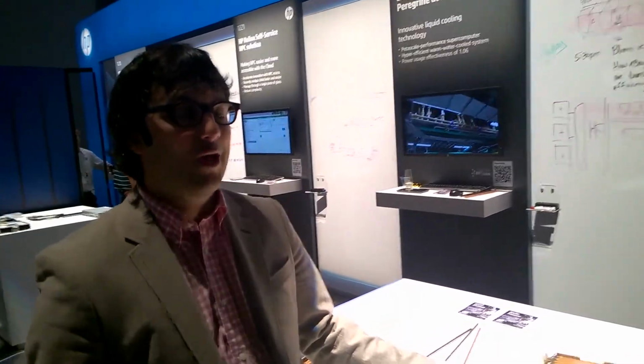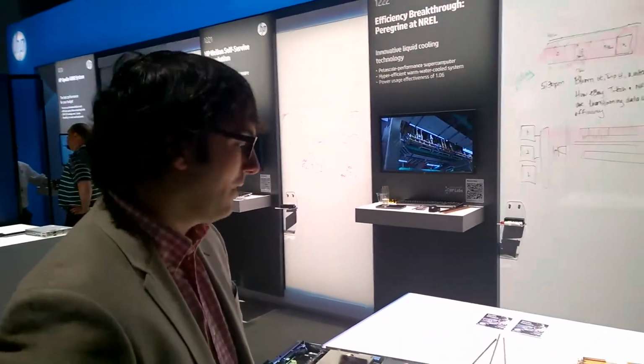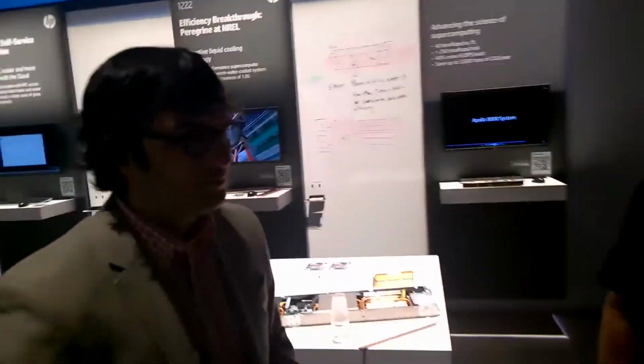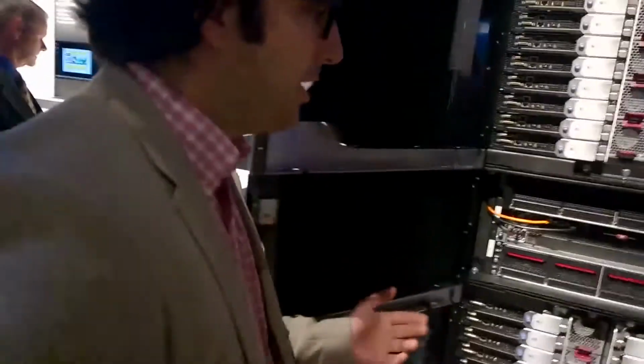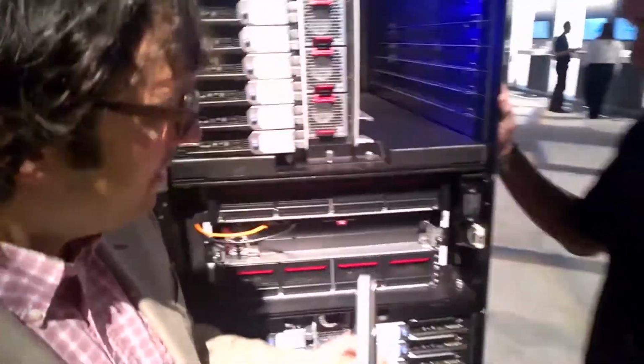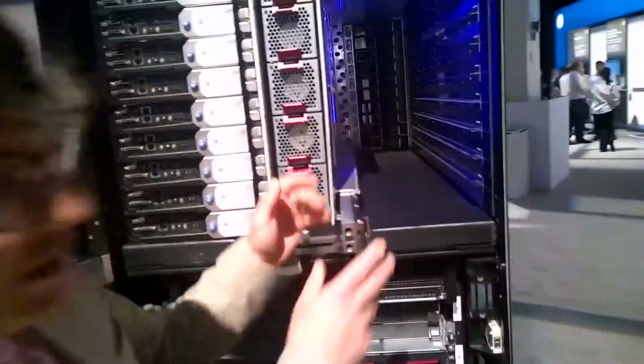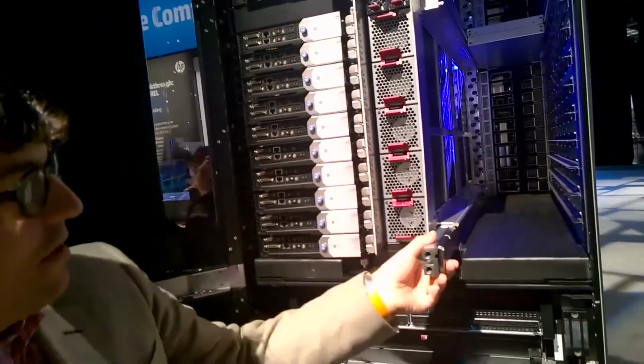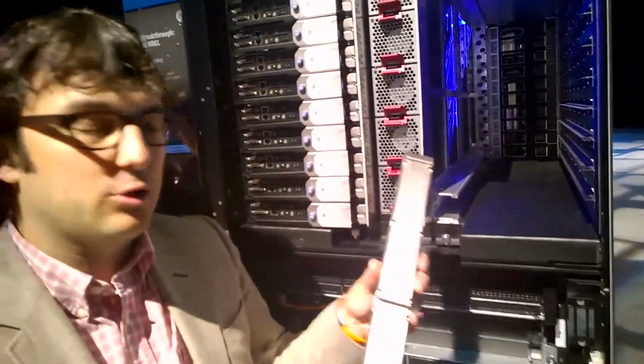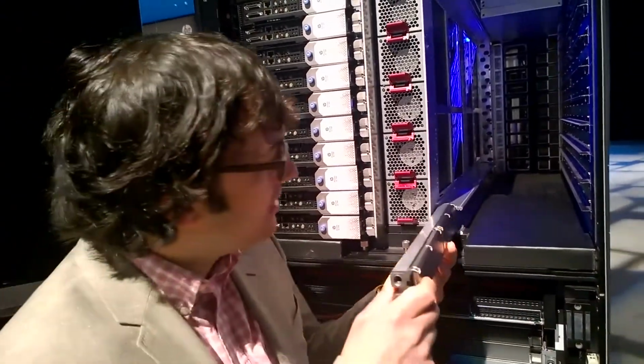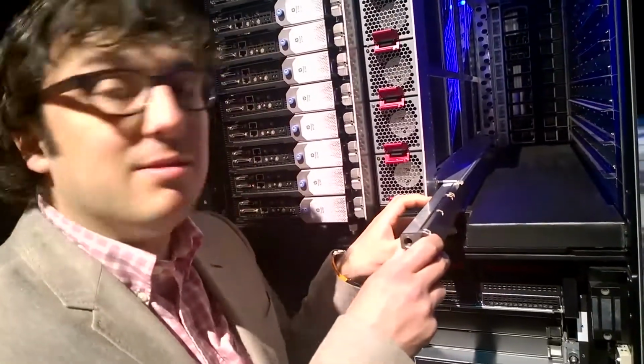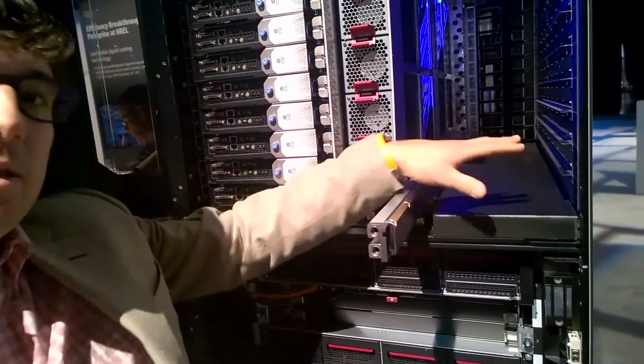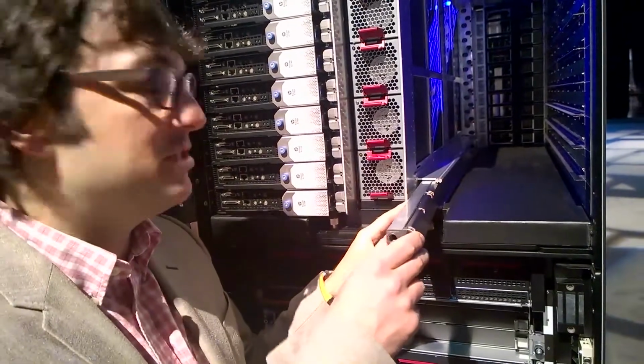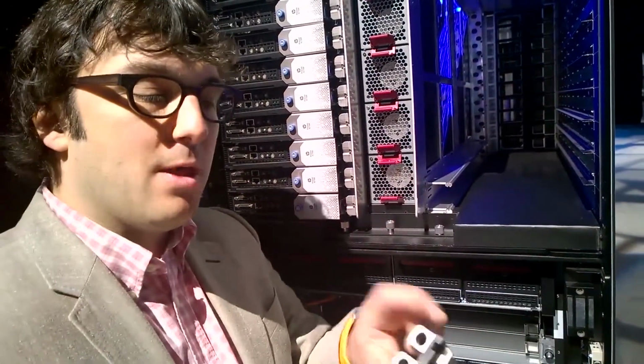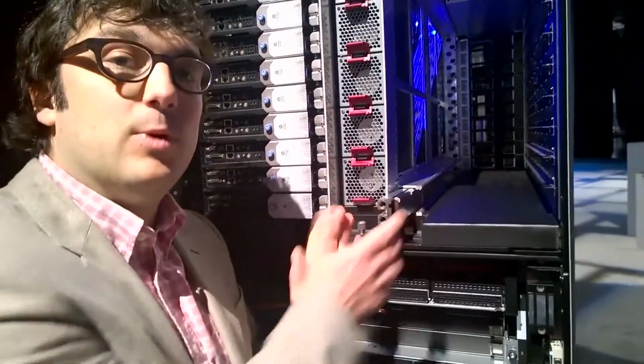That's awesome. Okay, so let's take a look at this. All right, so how do we do it? The main thing is really to have a servicing model that's quite unique. As you come in, you see that we have a vertical channel here that will have a whole bunch of units that we call thermal bus bars. The thermal bus bar is a unit that will come and make contact with the tray, and for all practical purposes, the compute tray always stays dry. The water flows through that unit here that always stays within the rack.